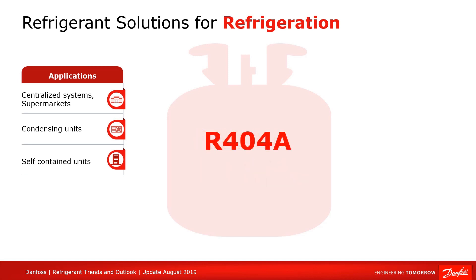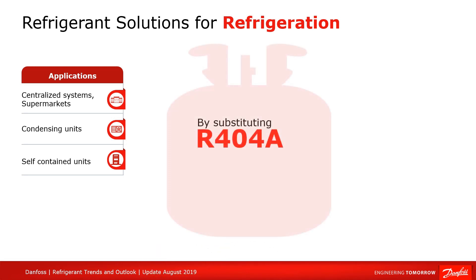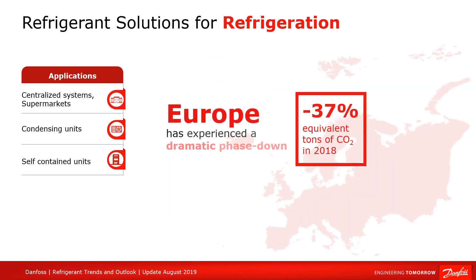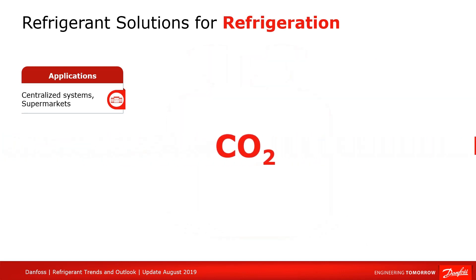Previously, commercial refrigeration primarily used R404A and R134A, but today R404A is on the decline. R404A has a high global warming potential and the emissions from many commercial systems can be reduced considerably by substituting R404A with an alternative. As I mentioned earlier, in 2018 Europe experienced a dramatic phase-down. The majority of this phase-down step came from refrigeration on the supermarket side due to shifts away from R404A and toward CO2.